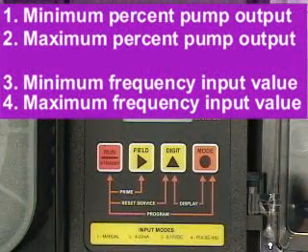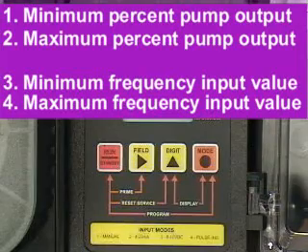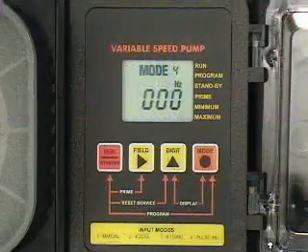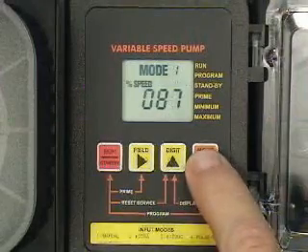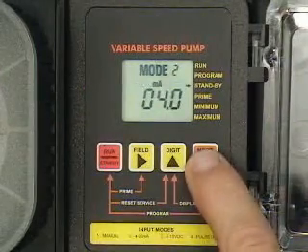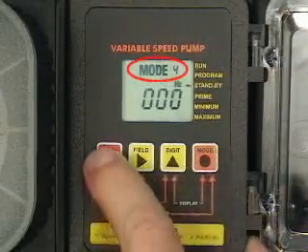Four values can be programmed: the minimum and maximum percentages of pump output and the corresponding minimum and maximum frequency input values. To set the pump for operating mode number four, press the mode button until mode four is shown on the LCD display.